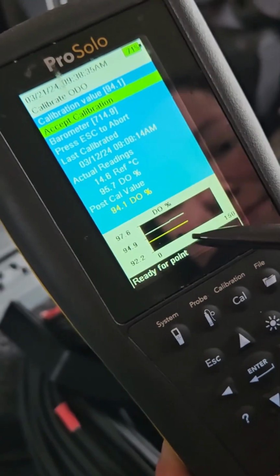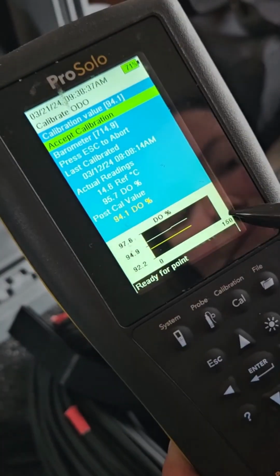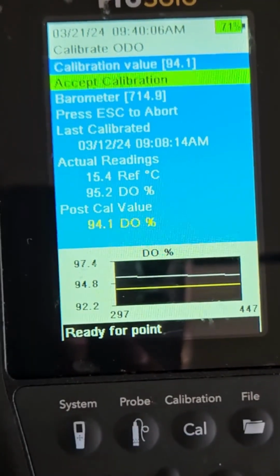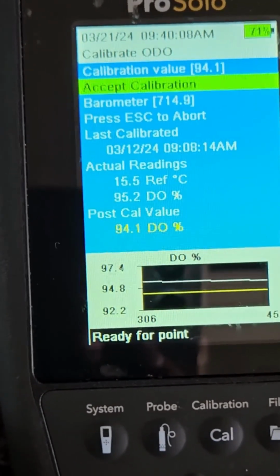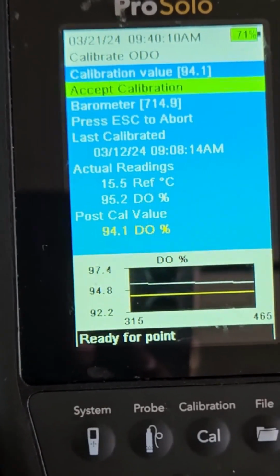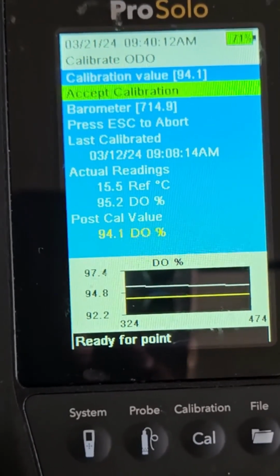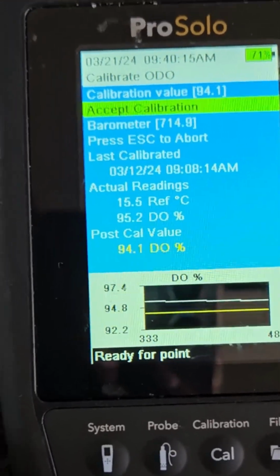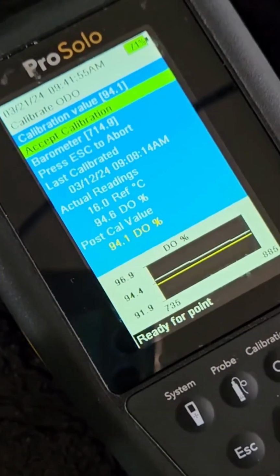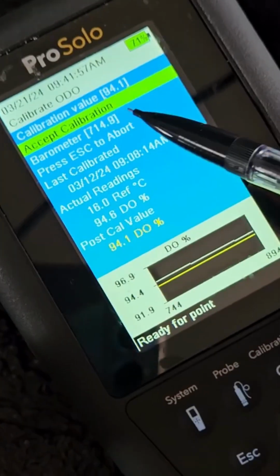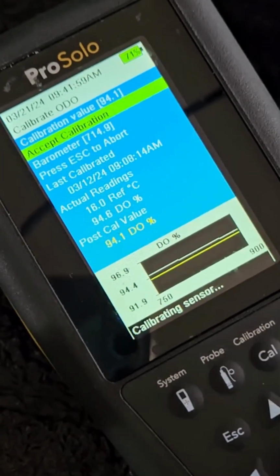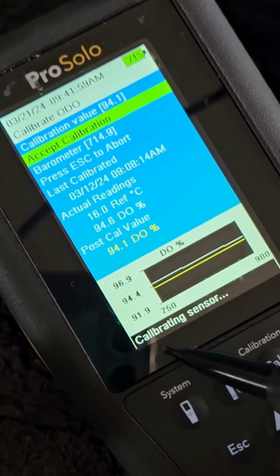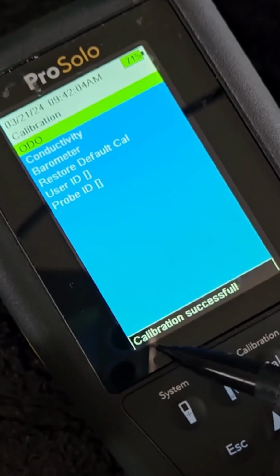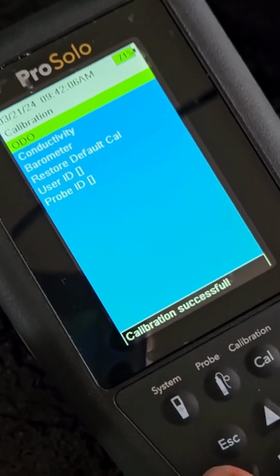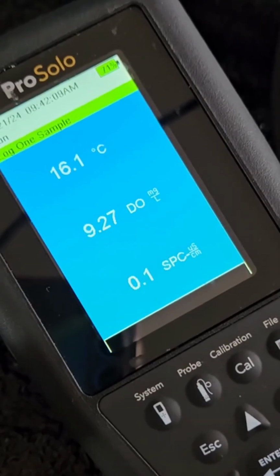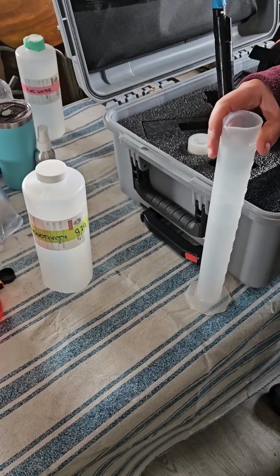And as it's calibrating, we'll see the lines go across the screen, and we want to make sure that there's no dips or spikes in the lines, just to make sure that it is stable. And once we're confident it is stable, we will accept this calibration. So we'll highlight that and press enter, and you'll see calibrating sensor, and it was successful. With this, you'll know that you've done it correctly and you're ready to go on to conductivity.